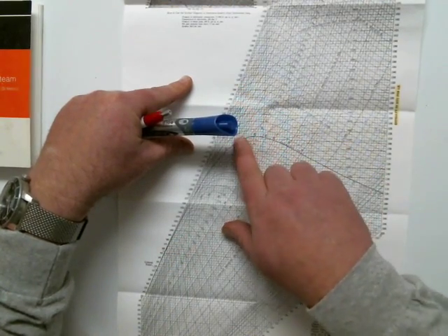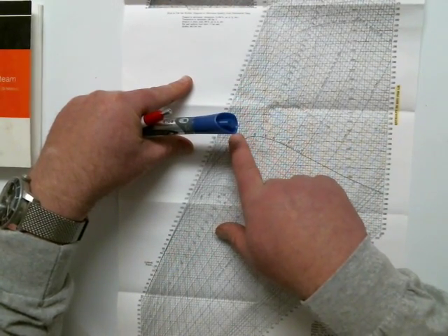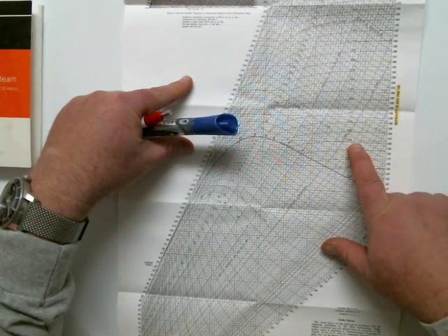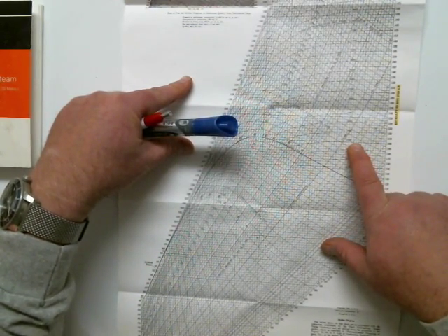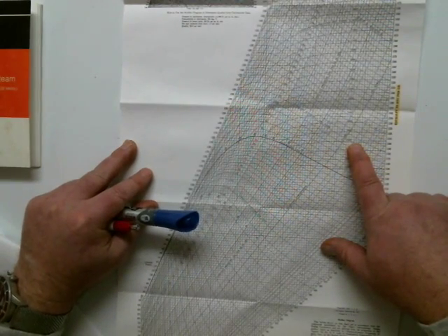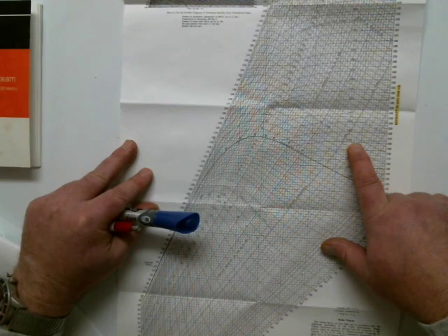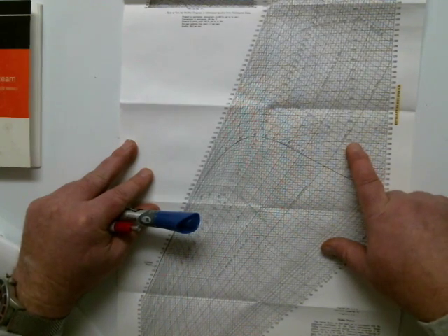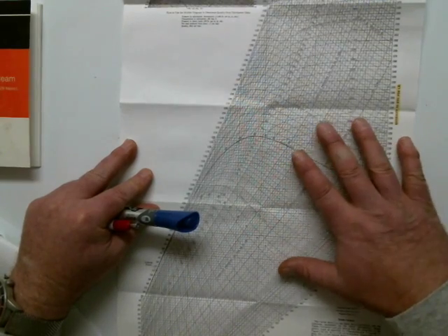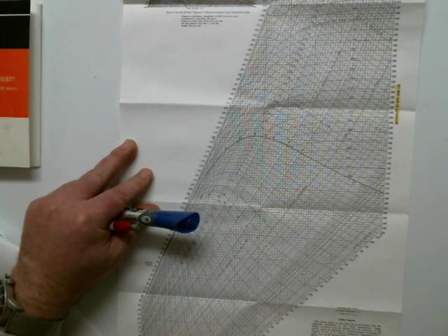You're going to go, oh, I'm at 544 degrees, and I'm going to open up the SRV, I should be at 544 degrees, but in fact, you're not. It's only at 320 degrees, and you may think, oh my heavens, it's just simmering. Well, that would be the same mistake that Three Mile Island made. And we're not going to make that mistake. We're going to understand how to use this Mollier diagram bulletproof so that doesn't ever happen again.